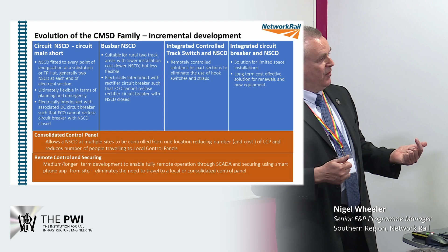We've also got an integrated DC circuit breaker and NSCD. So when we come to renewals of some of the older DC equipment, we can put in one piece of kit with two functions. That piece of kit is slightly more expensive, but it's one rather than two, and the cost of installation is massively reduced. It's a real game changer too, in tight spaces where there isn't room on the infrastructure to fit devices.